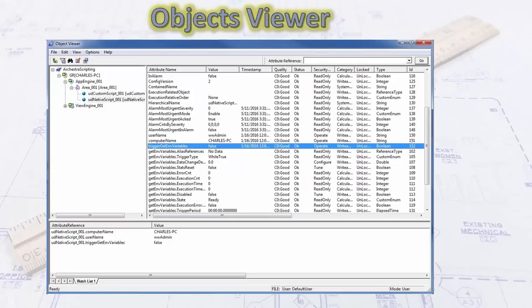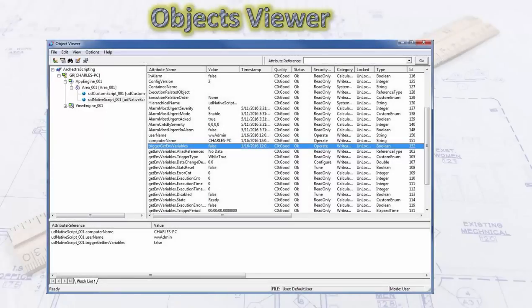Once an object has been instantiated, deployed, and is running on an engine, you can view what's inside it using the Object Viewer. To access it, browse to the object, right-click and select Object Viewer. In the upper left-hand corner you'll see an explorer pane showing which area, engine, and platform the object is running on. On the right are all the attributes inside that object.